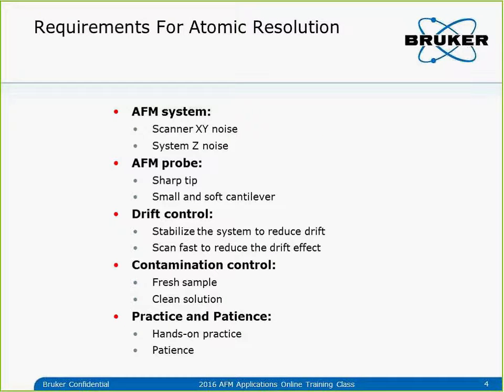Now let's talk about what requirements we need to meet to achieve atomic resolution. The first is the AFM system. We need a good AFM system. For the multimode, using the E-scanner or A-scanner is capable of atomic resolution because it has very low XY noise. Other systems like FastScan and ICON are also capable, as is the Innova system. The XY scanner noise is good enough for atomic resolution. We also need good Z system noise. In a good environment, all these systems can meet the atomic resolution requirement.